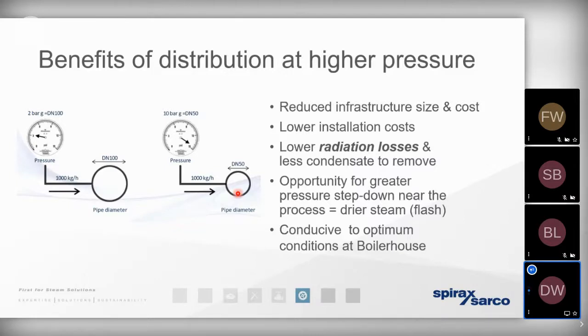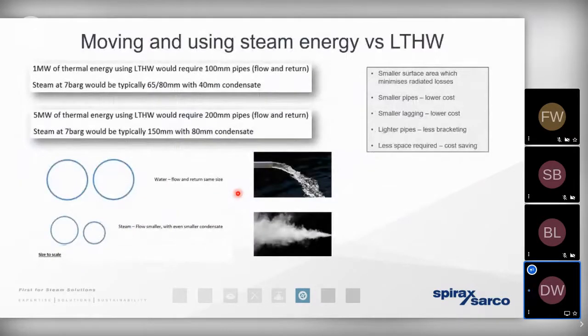And just taking that one step further with regards to understanding the benefits of distributing steam as a gas, and as a compressible gas at that. If we compare the distribution network for steam to low temperature hot water, we've already mentioned in previous presentations that steam has approximately 50 times the latent heat, the useful heat energy present in it, than a low temperature hot water system that could have been designed to give up 11 degrees of heat at the process. 50 times more energy. So of course we need to generate and then distribute 50 times less to get the same heating effect.